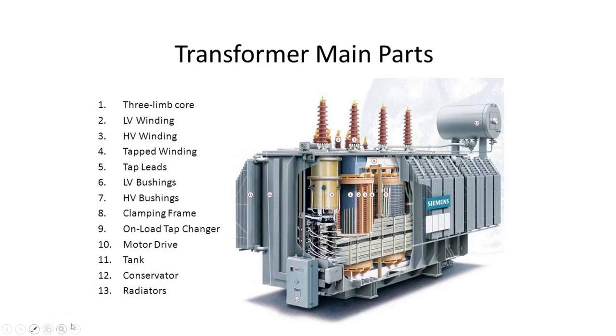Let's say the primary voltage is Vp and the secondary voltage is Vs. This is linked with the number of turns: Vp over Vs equals Np, the number of turns in the primary, divided by Ns, the number of turns in the secondary. Normally, without tap changers, the transformer has a fixed turns ratio. That means each particular transformer can transform with a fixed ratio. For example, we may have a transformer with 11 kilovolt to 66 kilovolt, for instance, with a fixed turns ratio.